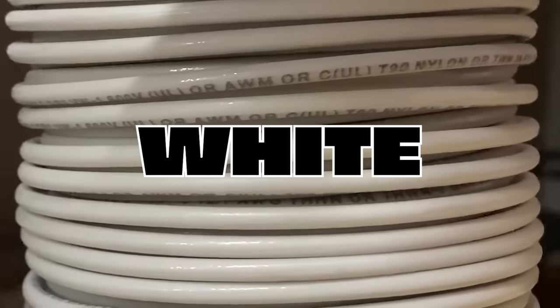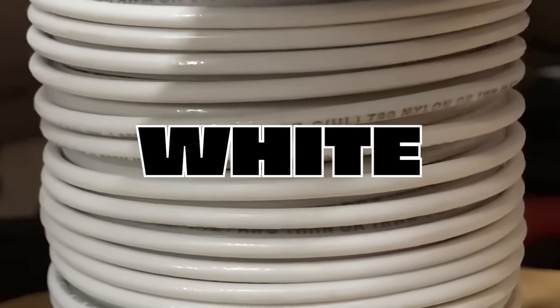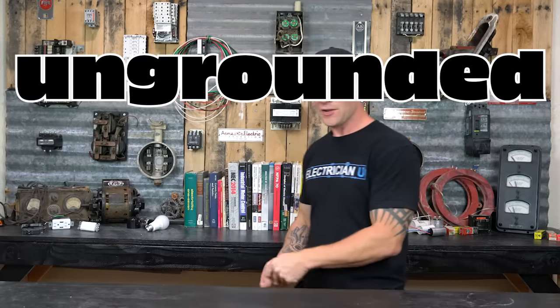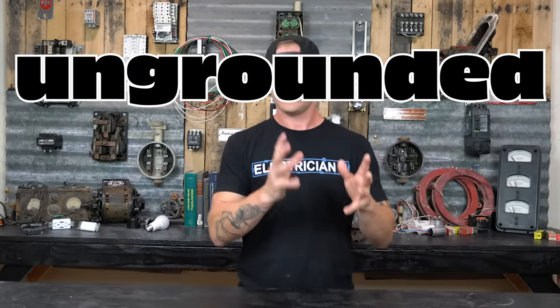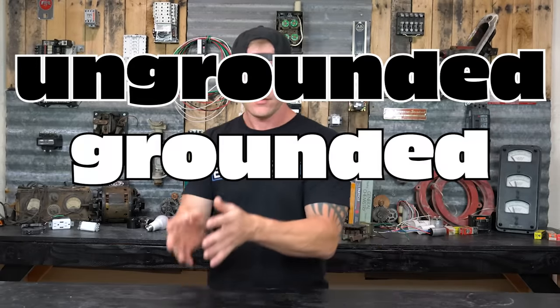Anytime you see a ground conductor, or if you see a green conductor with yellow stripes on it, that's another way they identify ground. Next, white is what we call neutral — also called the grounded conductor in the code book. There's a difference between a grounding conductor and a grounded conductor. Just remember: hot is ungrounded, meaning it's not touching ground at all. Ungrounded is hot, and grounded is neutral.